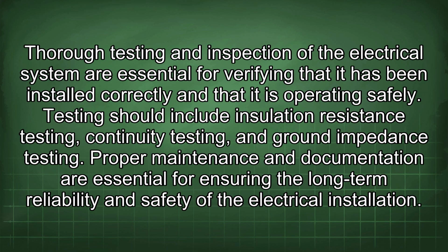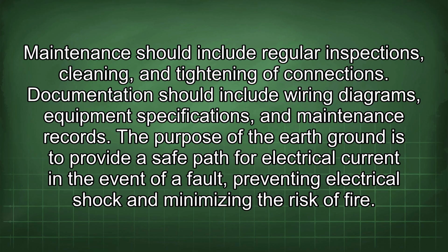Thorough testing and inspection of the electrical system are essential for verifying that it has been installed correctly and that it is operating safely. Testing should include insulation resistance testing, continuity testing, and ground impedance testing. Proper maintenance and documentation are essential for ensuring the long-term reliability and safety of the electrical installation. Maintenance should include regular inspections, cleaning, and tightening of connections. Documentation should include wiring diagrams, equipment specifications, and maintenance records.